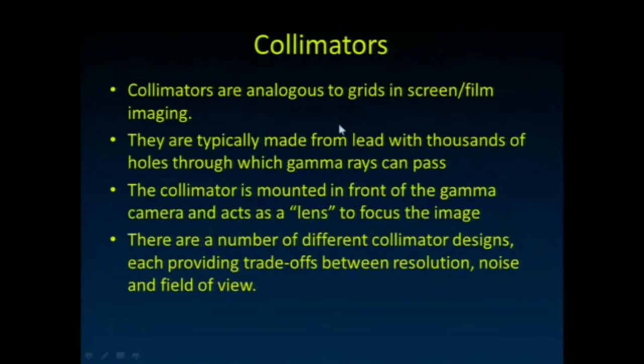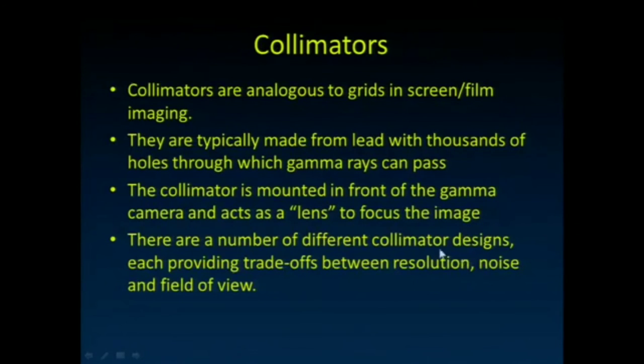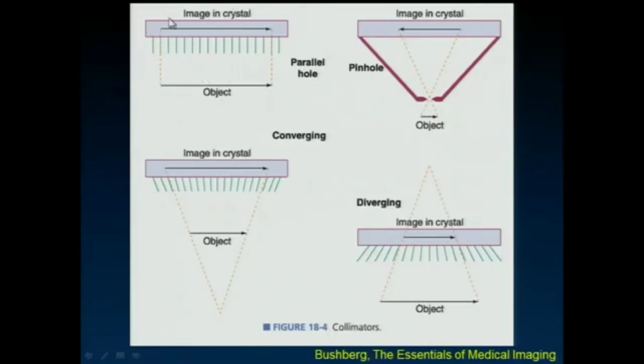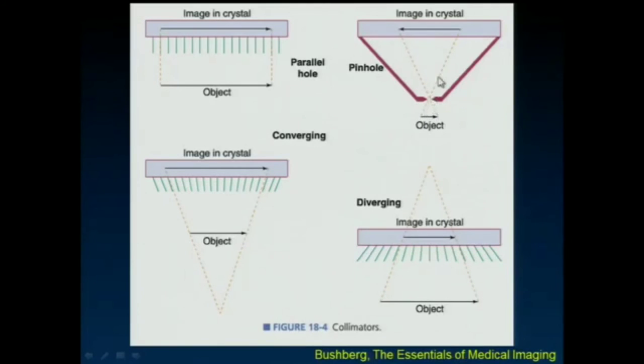Let's talk about collimators. They're typically made from lead and have thousands of holes through which gamma rays can pass. Mounted in front of the crystal, they act like a lens to only accept gamma rays coming from a particular direction. There are a number of different collimator designs, each providing trade-offs between resolution, noise, and field of view. A parallel hole collimator accepts only gamma rays traveling parallel to each other. A pinhole collimator works similarly to how x-ray imaging uses a point source — all gamma rays must travel through a single pinhole to form the image.